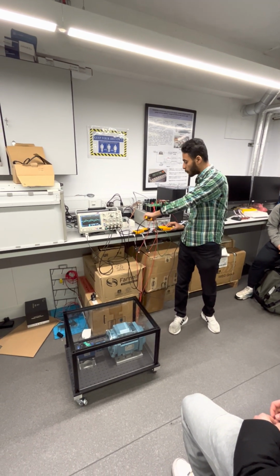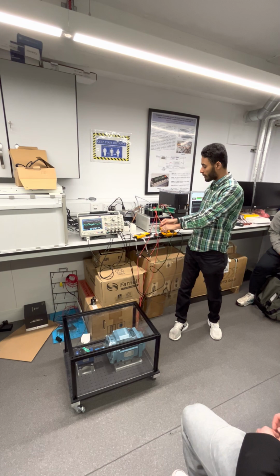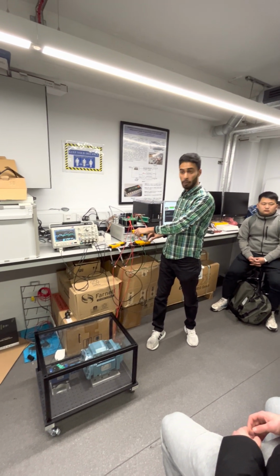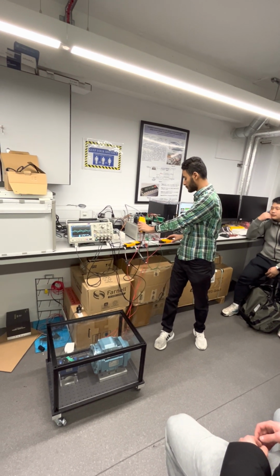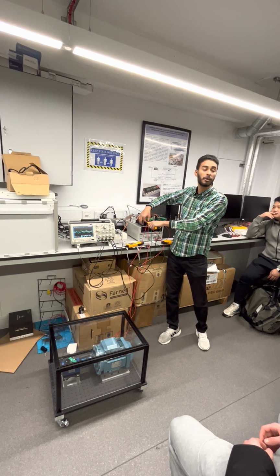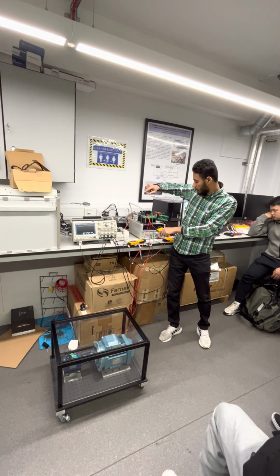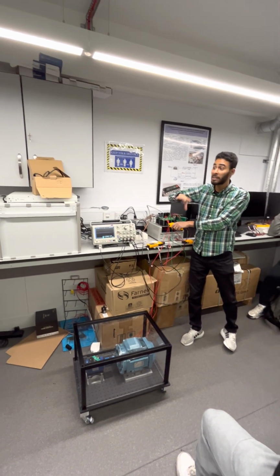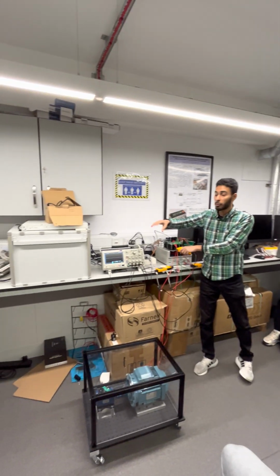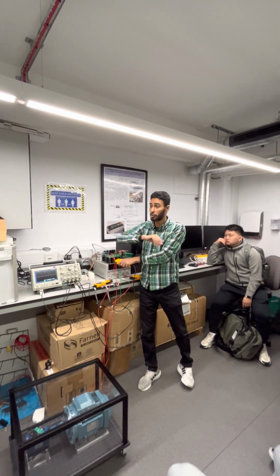You can see here that we can measure any phase, this phase, or the current of this phase, or even the third one. What will happen if we measure the 3 of them together? From here, if we measure the 3 of them, what will happen? Let's turn off this one and this one. It will be 0. Okay, so for balanced operation, we have to make sure that the 3-phase current is balanced, and the summation of the 3-phase current is 0, so this is an indicator for balanced operation.